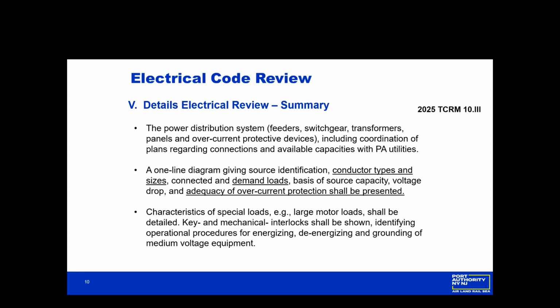Characteristic of the special load, for example, large motor load, shall be detailed. Key and mechanical interlock shall be shown, identifying the operational procedures for energizing and de-energizing and grounding medium voltage equipment. Next.